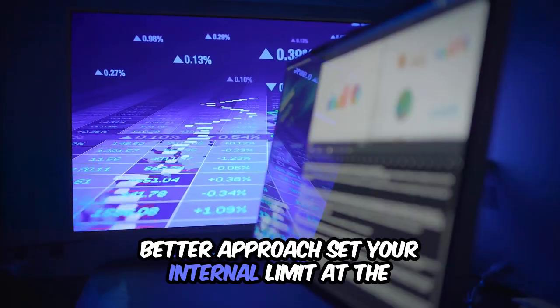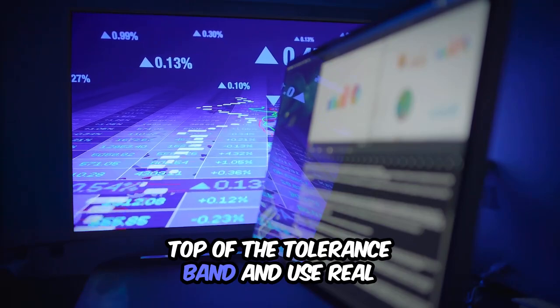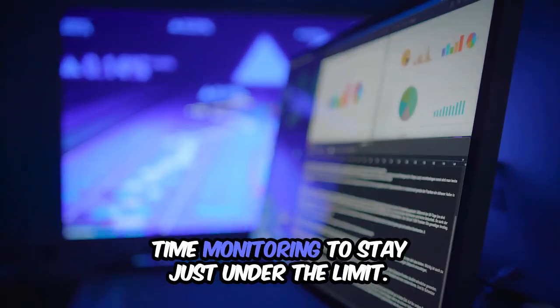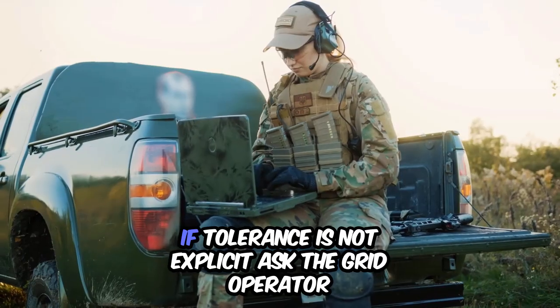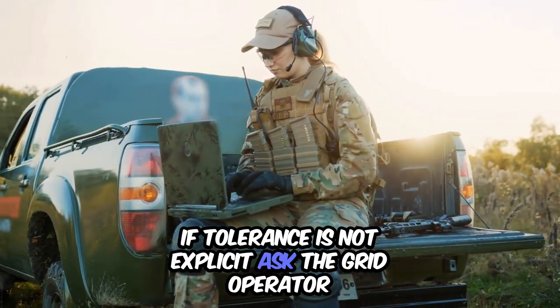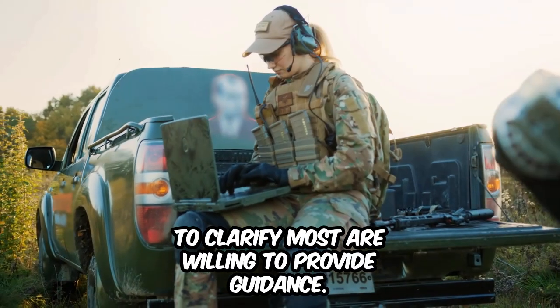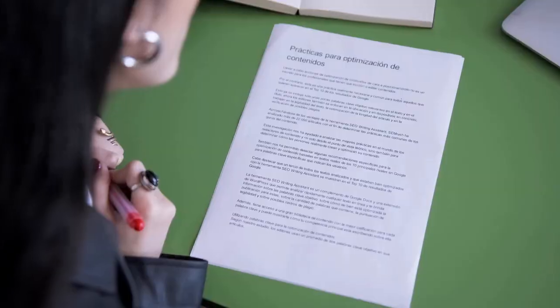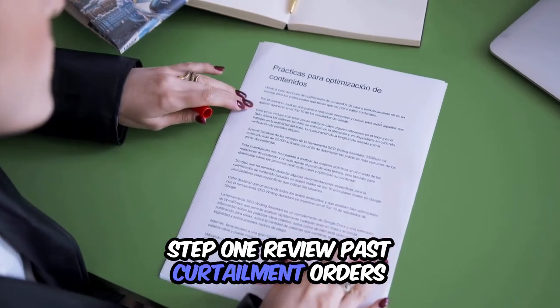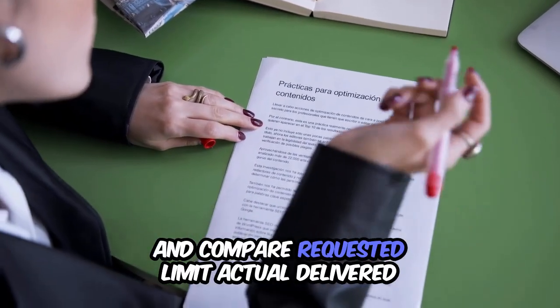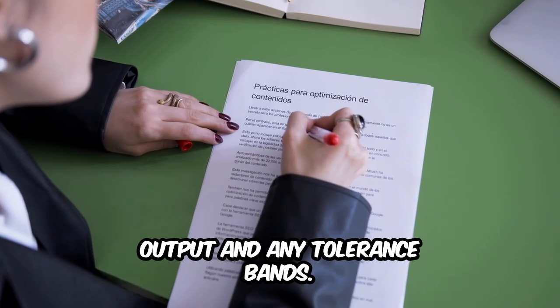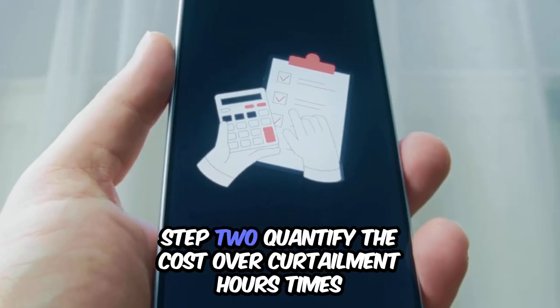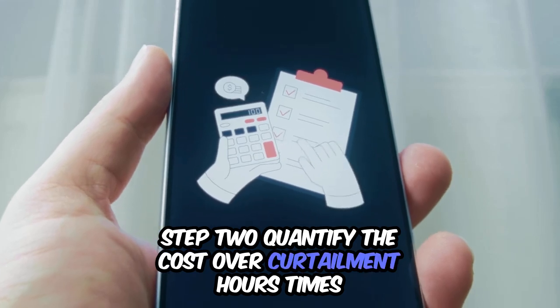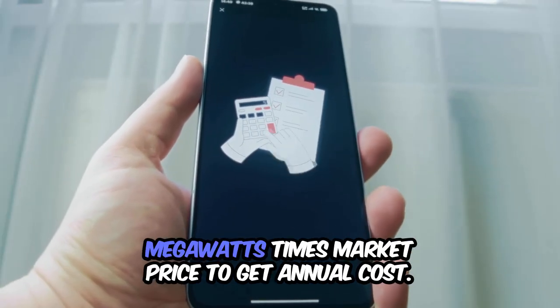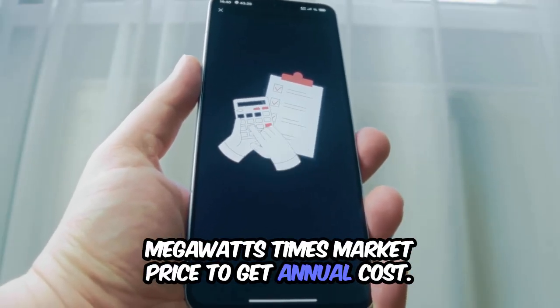Better approach: set your internal limit at the top of the tolerance band and use real-time monitoring to stay just under the limit. If tolerance is not explicit, ask the grid operator to clarify. Most are willing to provide guidance. Step 1. Review past curtailment orders and compare requested limit, actual delivered output, and any tolerance bands. Step 2. Quantify the cost: over-curtailment hours times megawatts times market price to get annual cost.